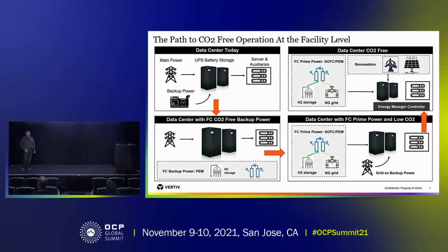So let's go to the bottom left. If we switch out the diesel generators and move over to hydrogen fuel cells, whether it's PEM or SOFC, to supply the batteries, now you're in a position over in the bottom right where you can supply grid power or battery from the hydrogen source as a carbon-free source, and the utility backup can be the actual backup.